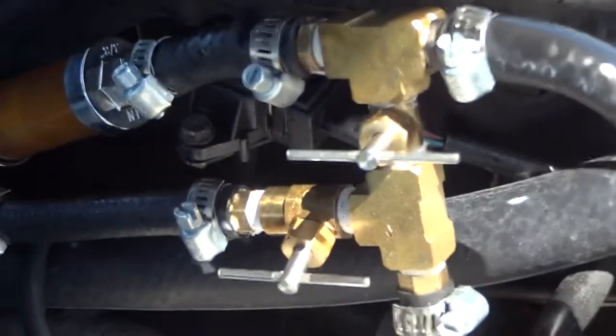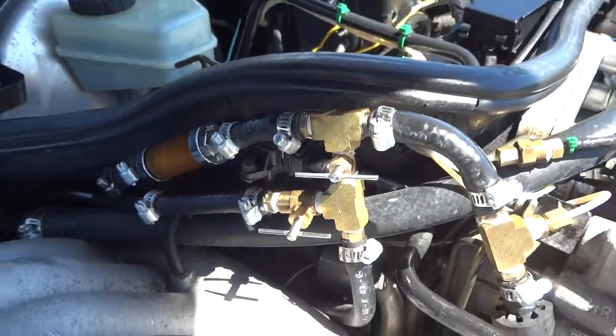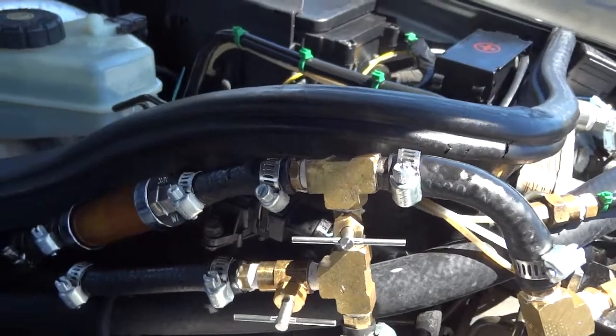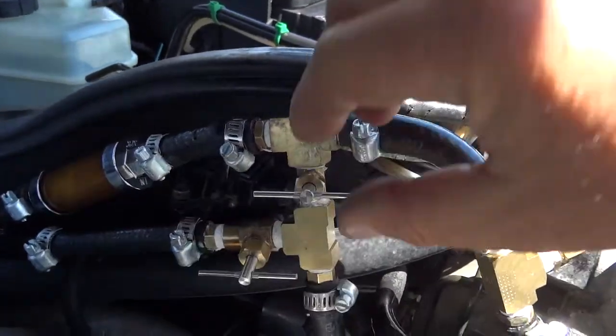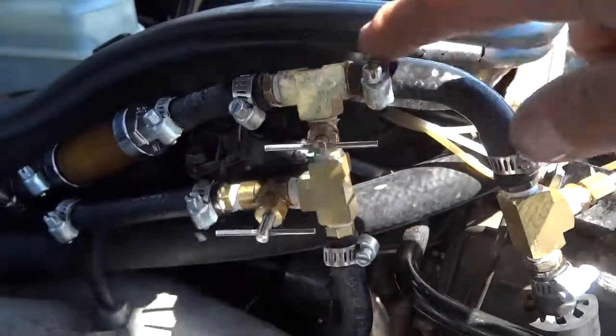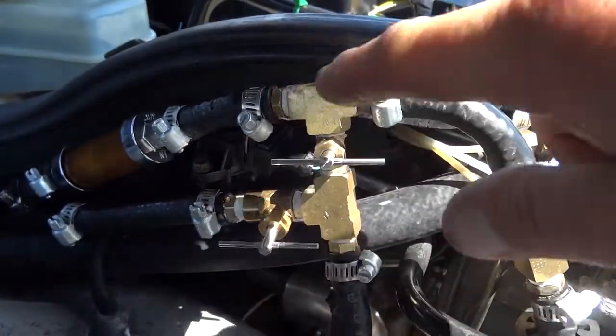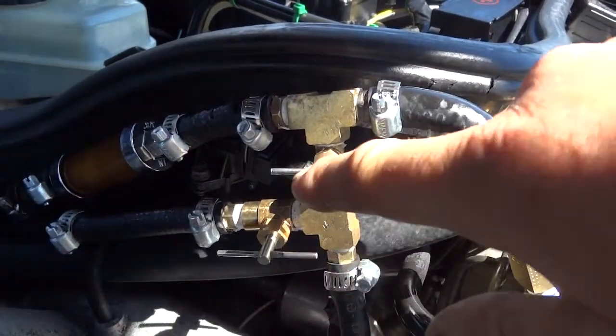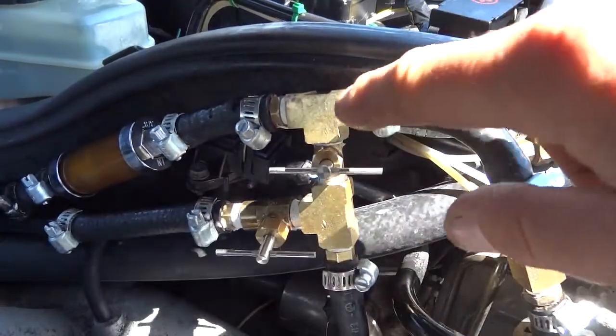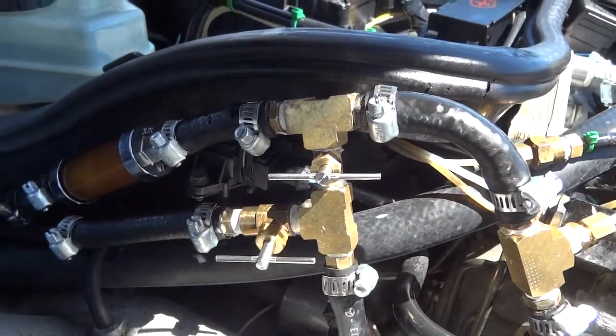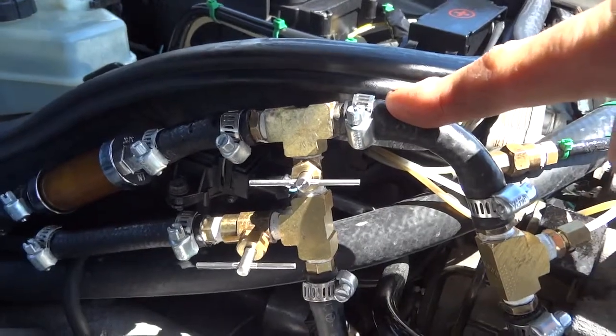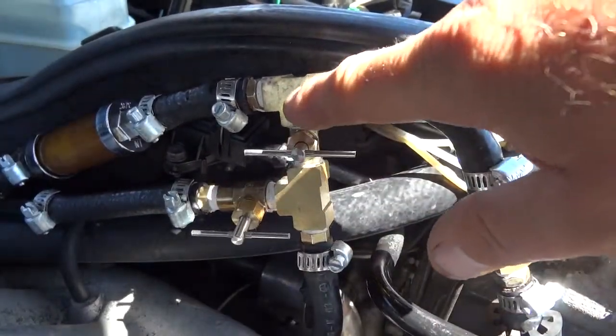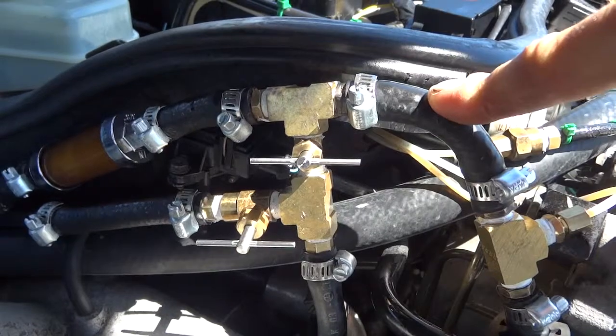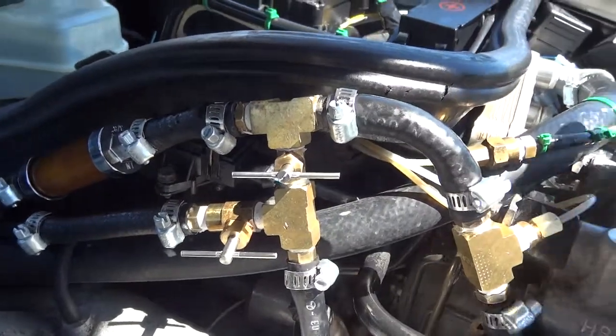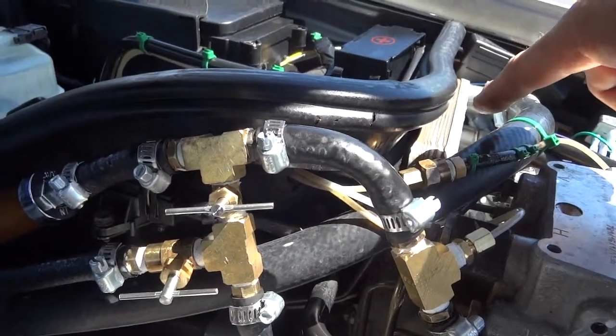So there's a little contraption here. With this I can adjust the fuel pressure. See, there's a little loop-back thing here. With this valve I can loop some of the fuel back to the injection pump, and that means it will get warm oil to begin with, even before it goes into the heat exchanger.